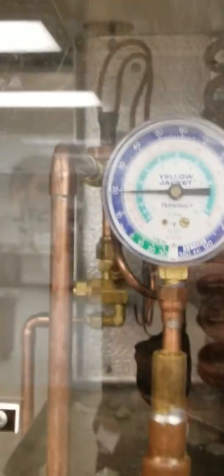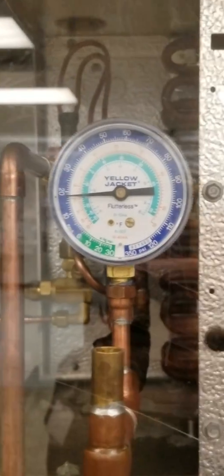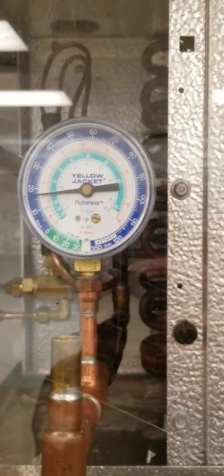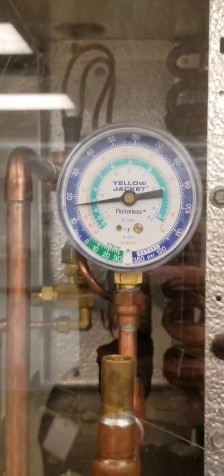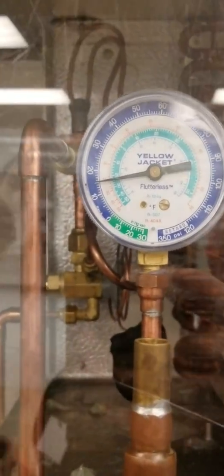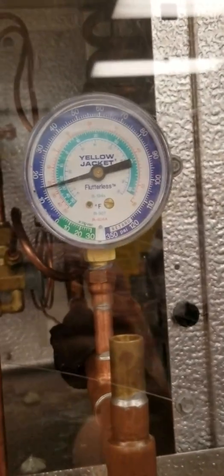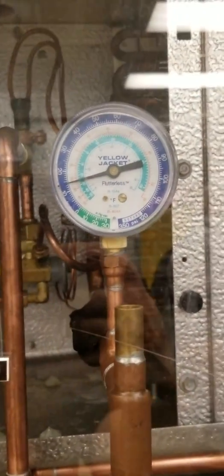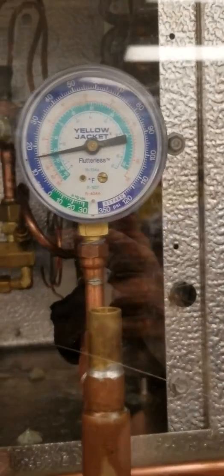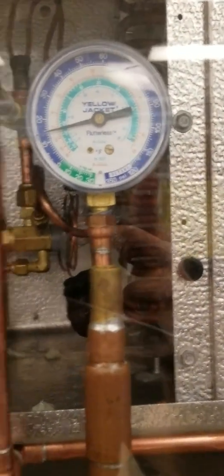Now this is getting cold here. This is cold right here. You have a pressure tap here. That evaporator pressure is going to drop, and as the pressure gets lower and lower, you're going to have your temperature sensor that's mounted onto the pipe. It's going to activate the fan. Your fan is sitting there in series, ready to come on, but your temperature switch has it open right now. And as it drops in temperature, it's going to close the switch and enable power to the fans.